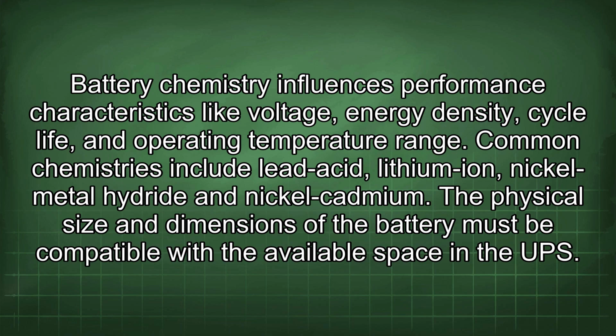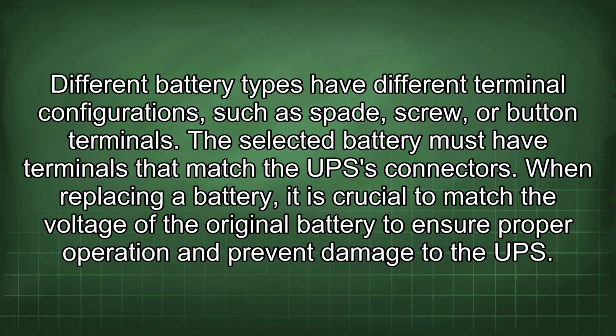The physical size and dimensions of the battery must be compatible with the available space in the UPS. Different battery types have different terminal configurations, such as spade, screw, or button terminals. The selected battery must have terminals that match the UPS connectors. When replacing a battery, it is crucial to match the voltage of the original battery to ensure proper operation and prevent damage to the UPS.